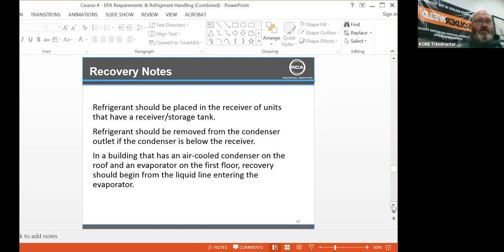Recovery notes. Refrigerant should be placed in a receiver of units that have receiver storage tanks. I'm sure guys are pumping down. I'm 100% confident that the Idaho Falls guys are pumping down refrigerant into the receivers when they make their repairs. Refrigerant should be removed from the condenser outlet if the condenser is below the receiver. That makes sense? I haven't seen many of those, but I'm sure they're out there.